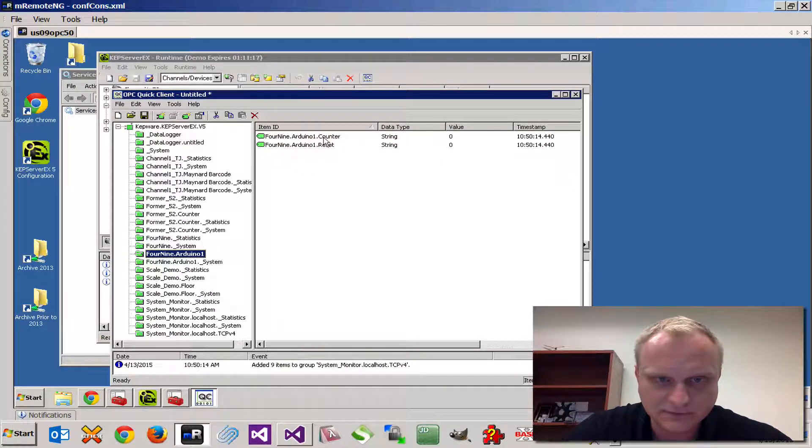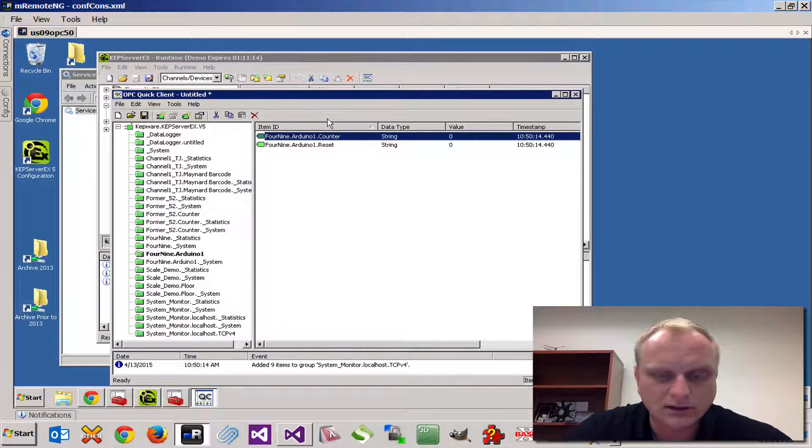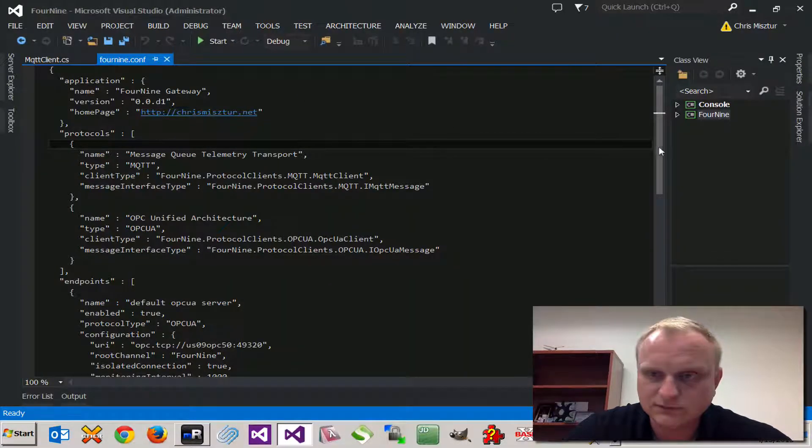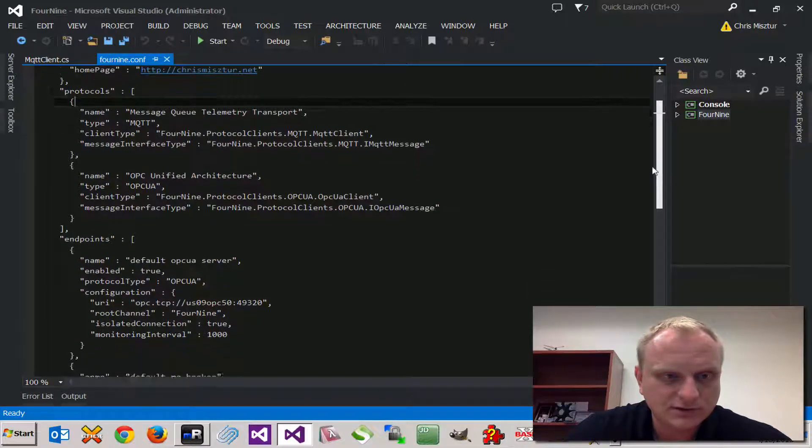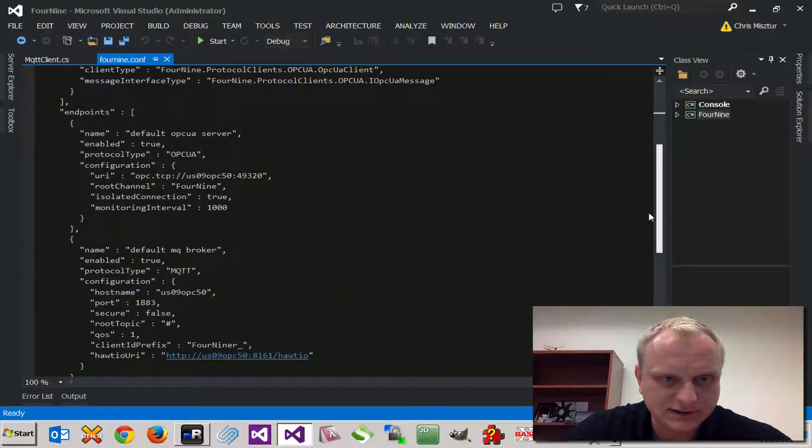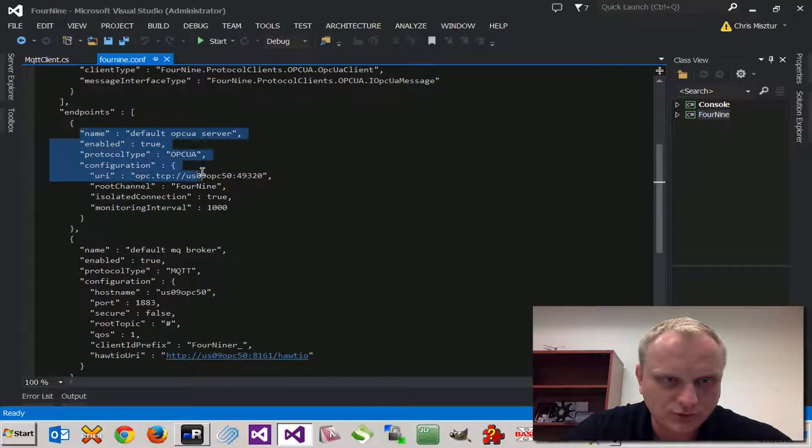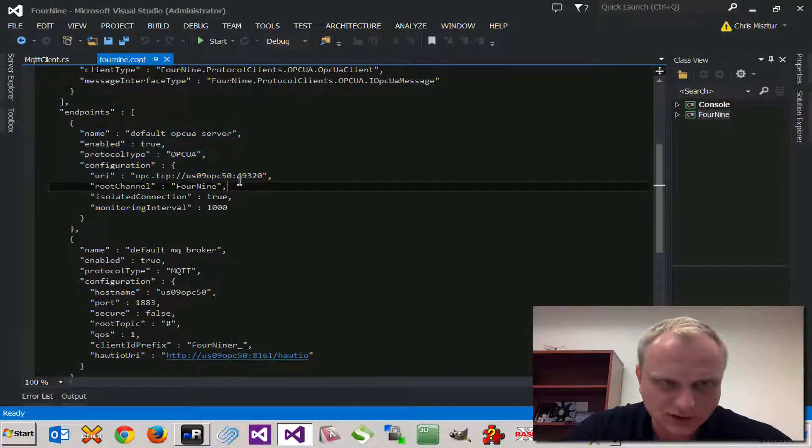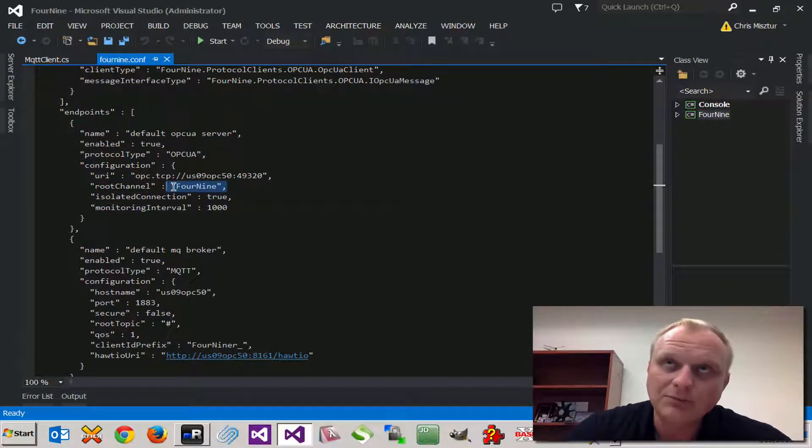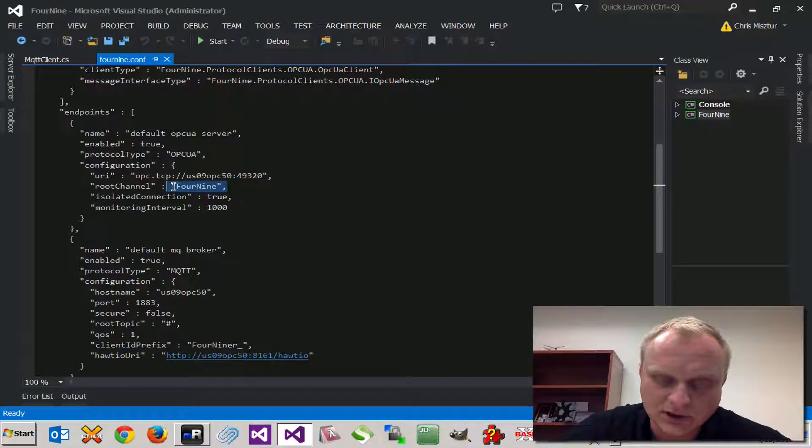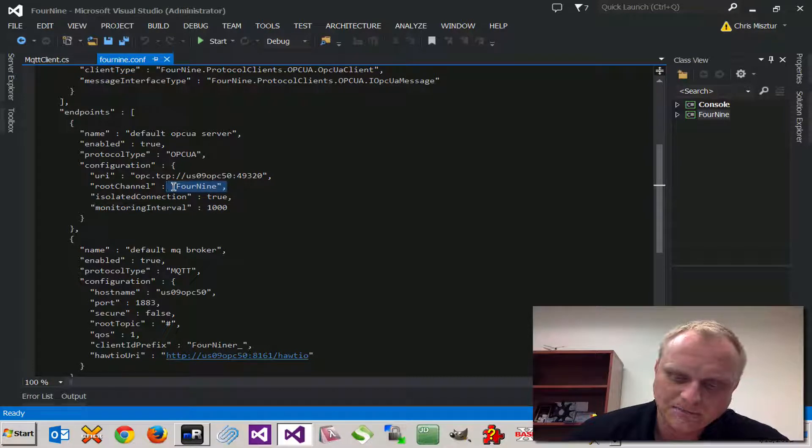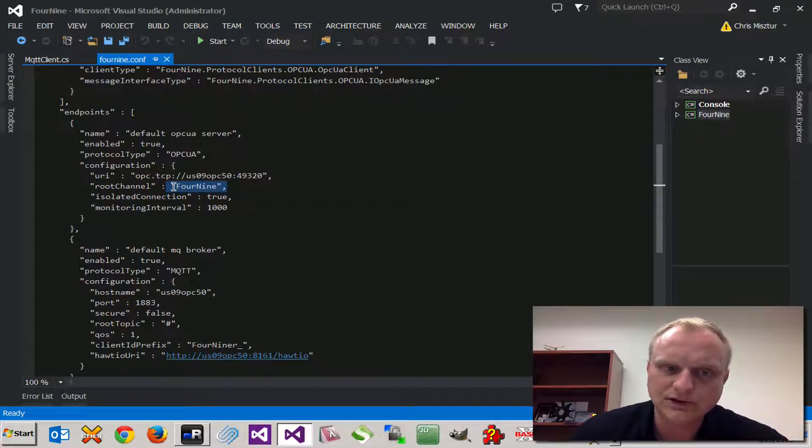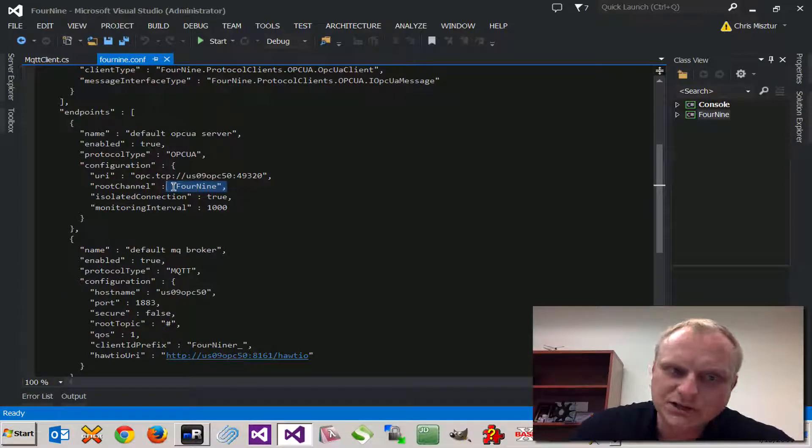Let me start up the FourNine bridge which has a couple connections defined here: the default OPC UA server we're going to be using and the root channel. What is going to happen is the bridge is going to subscribe to all the devices and all their tags, and it's only a single level deep right now on the FourNine channel. So any changes to the values on the OPC UA side are going to be brought back and dispatched to all the other protocols.